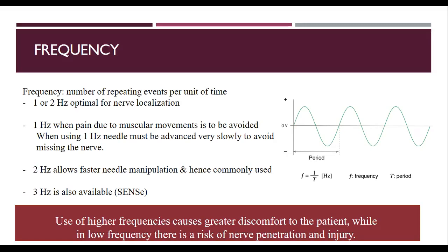3 hertz is also available, that is called SENSE, that is sequential electrical nerve stimulation. Use of higher frequencies causes greater discomfort to the patient, while in low frequency there is a risk of nerve penetration and injury. So it is important to understand whether to keep 1 hertz or 2 hertz. Usually we keep 2 hertz, that is the most commonly used. 1 hertz you can keep when more muscular movement is to be avoided, that can lead to discomfort or pain to the patient.